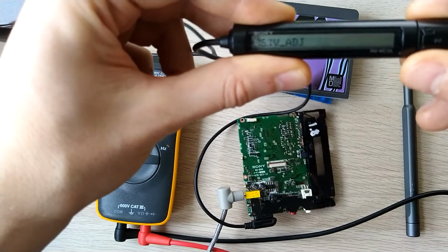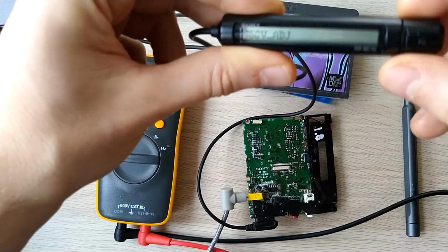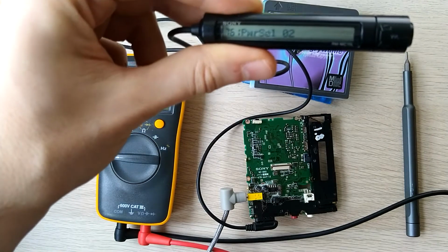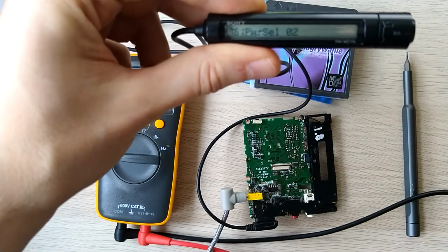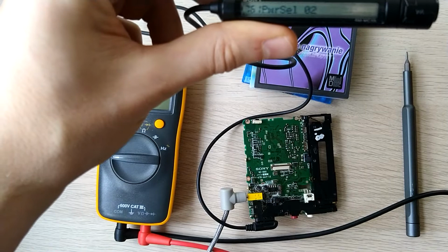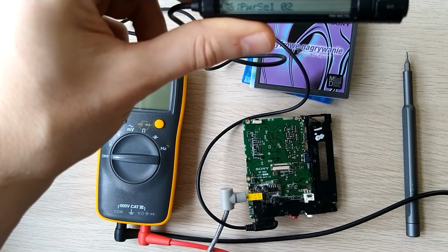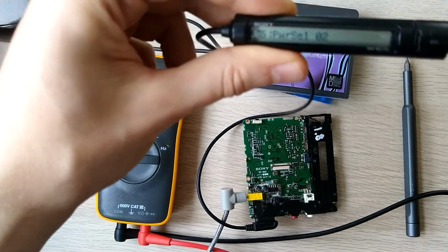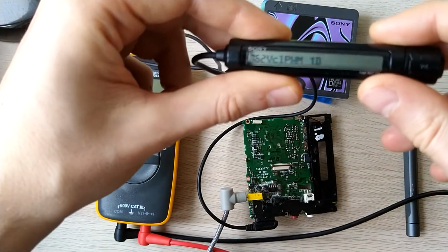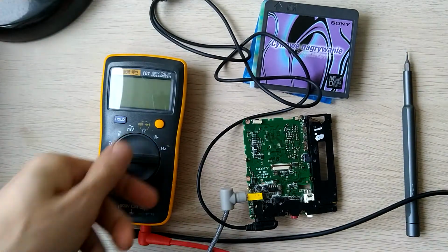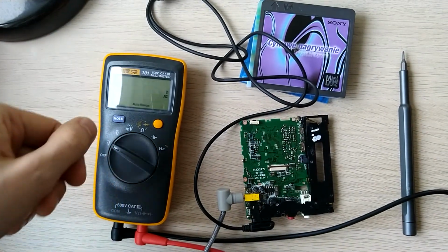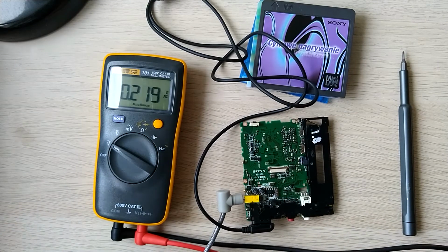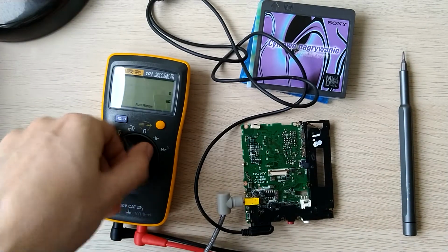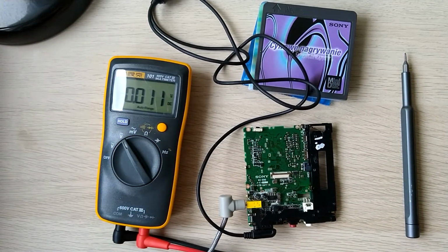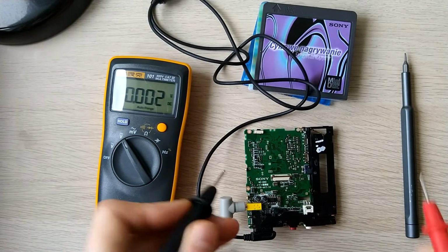762. So this is the voltage adjustments. The first item that we need to check, I'm just going to have a look in the service manual. Yeah, so the first item is 762, which is VCL PWM, and the service manual instructs us to measure the voltage between the ground and test point 915. So I'm just going to put my voltage meter in DC mode, and we measure the voltage.